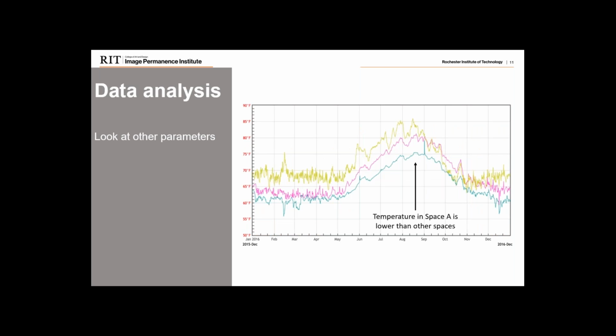And when we go to look at temperature, we can see that there is a difference here in temperature. Space A is at a lower temperature than the other spaces. Because they all responded to the outside dew point in the same way, we know that it's not necessarily a difference in moisture that is causing this high relative humidity, but rather a result of the same high moisture but a lower temperature. And because of that inverse relationship, the higher temperatures in the other spaces are able to artificially suppress the relative humidity in those other rooms.